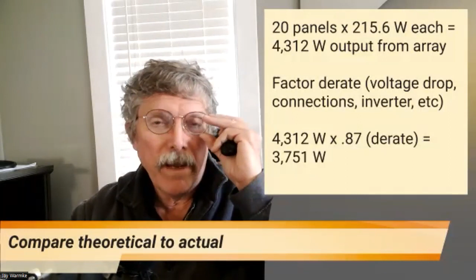Well, if you go and look at the output from the inverter, it's not going to be 4,312 watts, because now we've got to apply the derate. The derate factor is basically all of the system losses from the output of the panel to the output of the inverter. How much are we losing through this process? Those of you who have gone through my class go through that process. You say, okay, first we've got to calculate voltage drop.